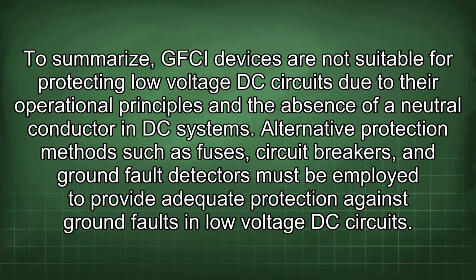To summarize, GFCI devices are not suitable for protecting low-voltage DC circuits due to their operational principles and the absence of a neutral conductor in DC systems. Alternative protection methods such as fuses, circuit breakers, and ground fault detectors must be employed to provide adequate protection against ground faults in low-voltage DC circuits.